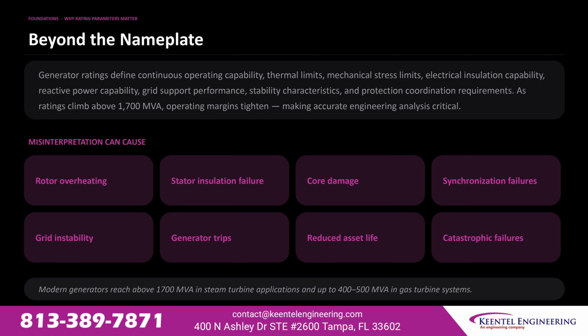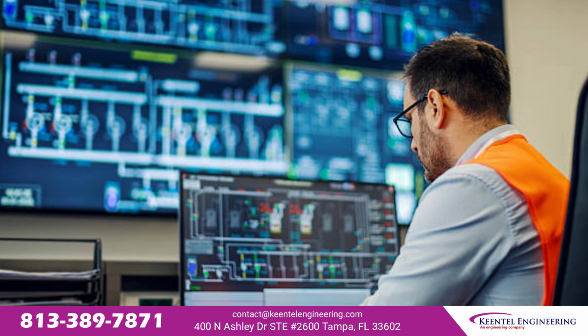Let's get into it. Generator ratings define continuous operating capability, thermal limits, mechanical stress limits, insulation capability, reactive power capability, grid support performance, stability characteristics, and protection coordination requirements. As ratings climb above 1,700 megavolt amperes, operating margins tighten, making accurate engineering analysis critical. Misinterpreting these parameters can cause rotor overheating, stator insulation failure, core damage, synchronization failures, grid instability, generator trips, reduced asset life, and catastrophic failures. Modern generators reach above 1,700 megavolt amperes in steam turbine applications and up to 400 to 500 megavolt amperes in gas turbine systems.